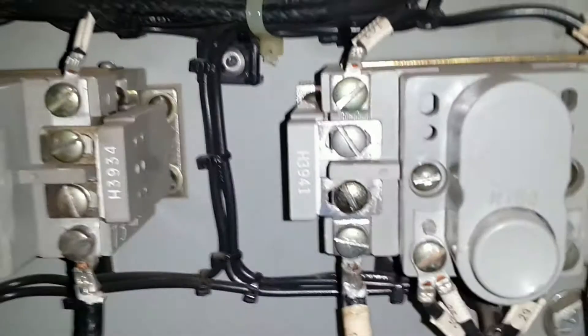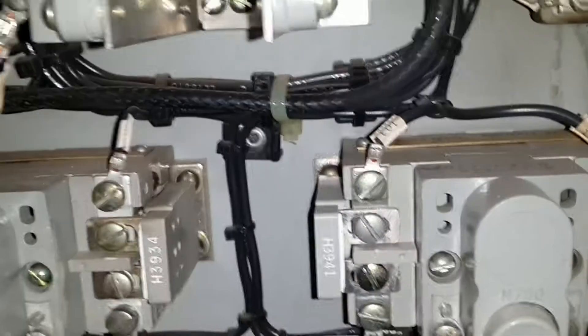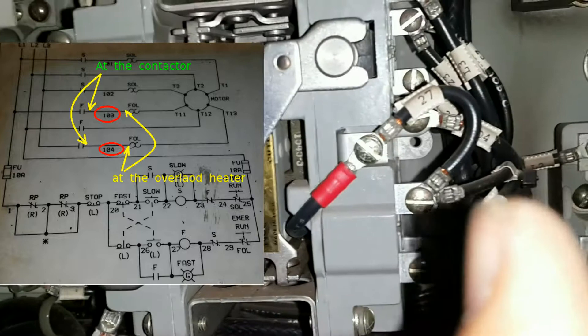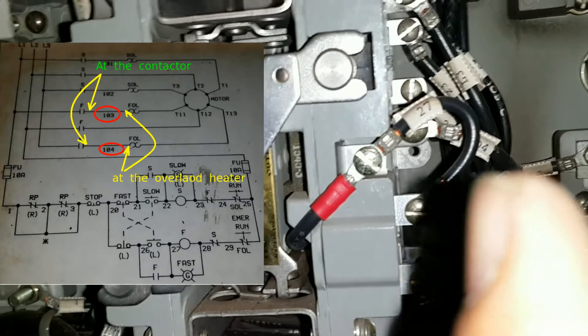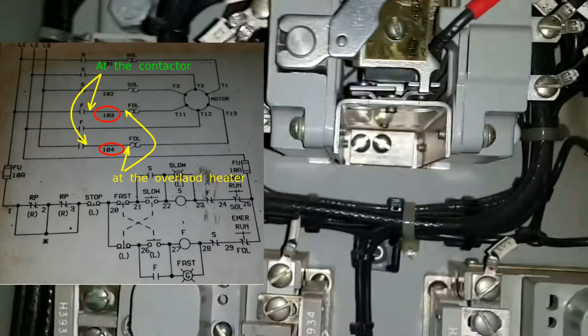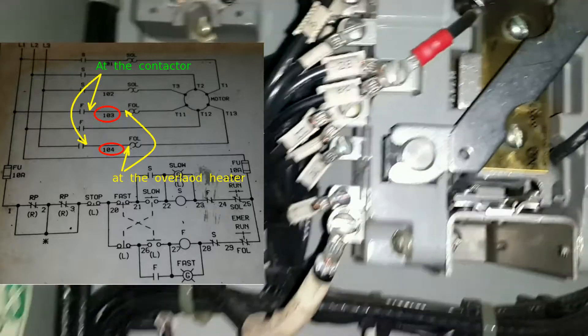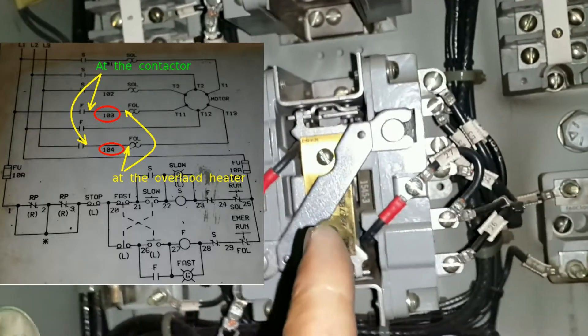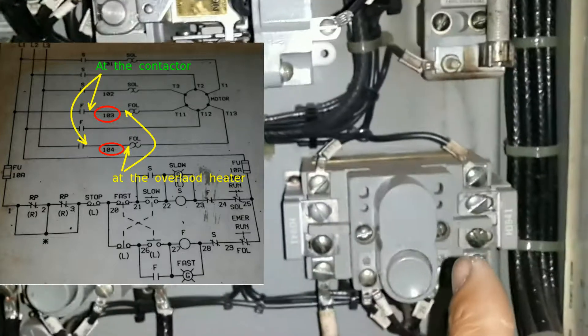The overloads: the top over here, so we got this one, this one over here, we got 104 and 103. That means it's associated with the contactor right there, 104. I cannot see 103 on the back of it, but the fact that 104 is over here means that the cables from here are going into this overload here.